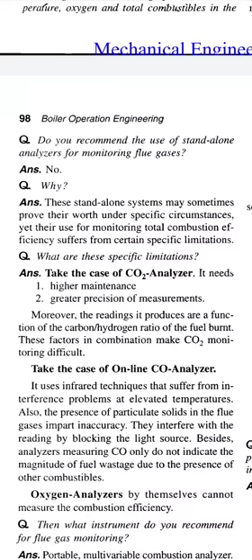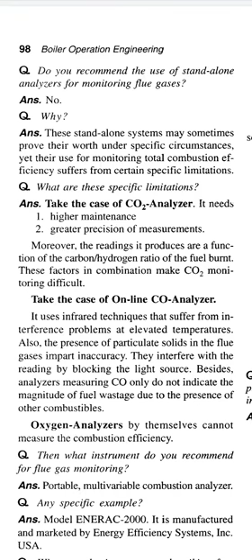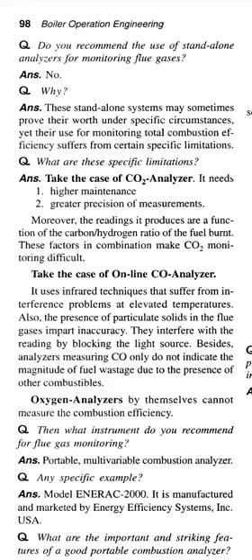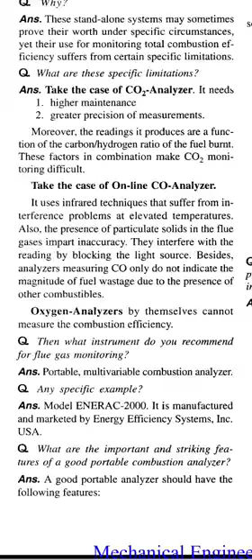Take the case of the online CO analyzer. It uses infrared techniques that suffer from interference problems at elevated temperatures. Also, the presence of particulate solids in the flue gases impacts accuracy. They interfere with the reading by blocking the light source. Besides, analyzers measuring CO only do not indicate the magnitude of fuel wastage due to the presence of other combustibles. Oxygen analyzers by themselves cannot measure the combustion efficiency.